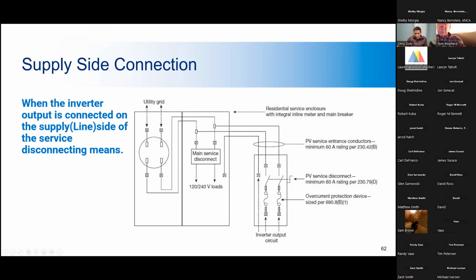and it must contain overcurrent protection, fuses, or circuit breakers, which you can see here. And at a minimum, the fault current rating should match that of the existing service equipment. And it needs a 60 amp rating for entrance conductors per code. That's very important. That's a code requirement. So you have to make sure that the entrance conductors coming in over here are rated for 60 amps.